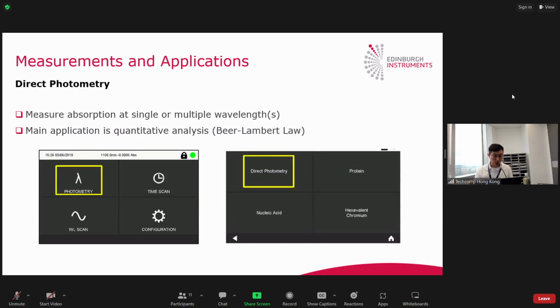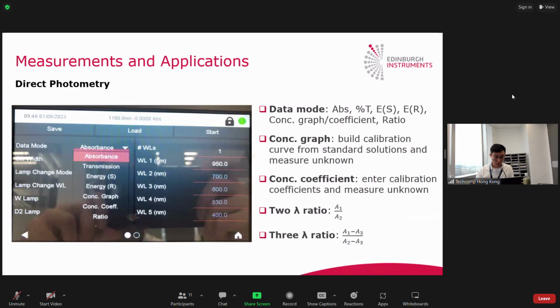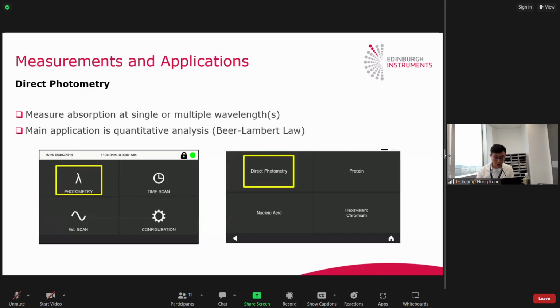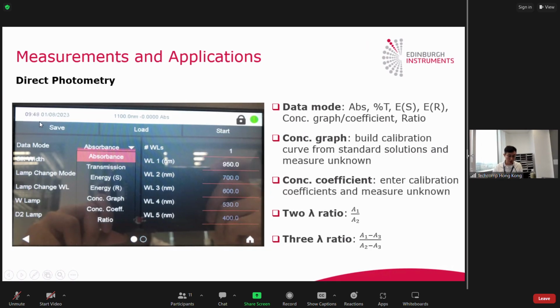So basically, the most basic measurement operation mode is direct photometry. You can choose photometry here, and then you can enter direct photometry. Direct photometry is used to measure the absorption at a single or multiple wavelengths, and according to the Beer-Lambert law, it is mainly used in quantitative analysis. So when you enter direct photometry, you will see the direct photometry setting screen. We showed it here.